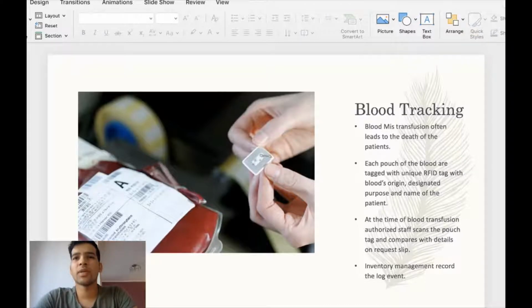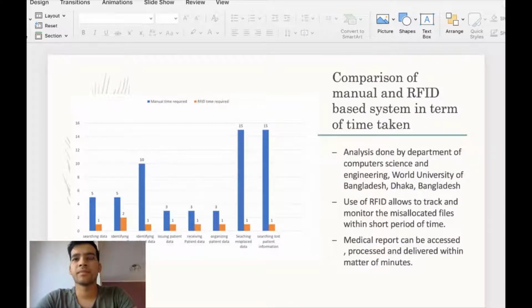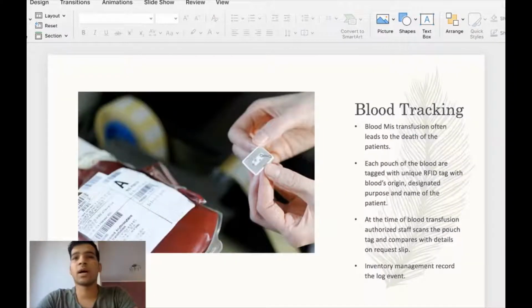Once the confirmation is done, the staff identification card is scanned to open the fridge door. Once the door is opened and closed, the inventory management system analyzes which product has been removed from the fridge and displays it on the screen. If an incorrect product is chosen from the fridge, the system generates an alarm and alerts the staff member.